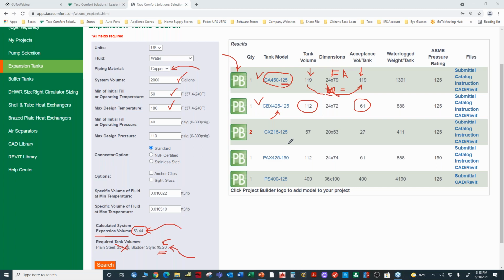And the third one, if you'll notice, the steel tank is 57 gallons. Well, it has to be a minimum of 95. So if you multiply by the quantity 2 here, if we put that in red to emphasize, that would be 57 times 2, which would be 114. And 114 is greater than 95, so it meets that criteria. Put a little check mark there. And the acceptance volume is 27 gallons. We multiply that by 2, so that comes out to 54 gallons. And the fluid is expanding 53.44, so it meets that criteria for 2. So that expansion tank will also work. And the same thing holds true for the others, but we're not going to talk about the plain steel tank this evening. If we have some time, we'll come back to it.